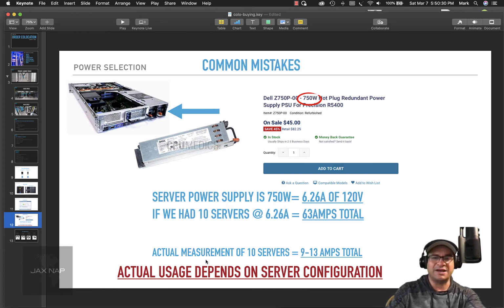But the actual measurement of the 10 servers can be anywhere from 9 to 13 amps total after you actually measure it. The actual usage depends on the configuration: how many hard drives you put in, how much memory, how much CPU, and what kind of process it's running. Is it crunching a lot of CPU? Then the CPU runs hotter, the fans kick up, and therefore it's utilizing more. So this is a common way to size up your power. Don't go by the power supply itself, go by the actual measurement of amps of the server.